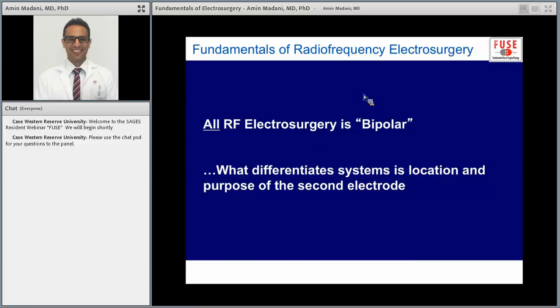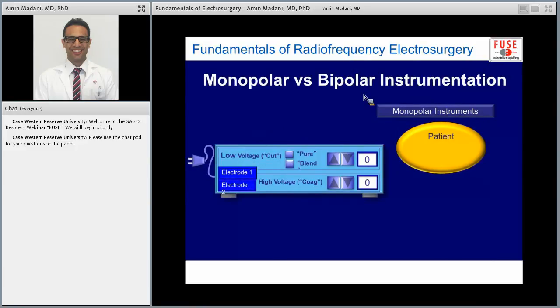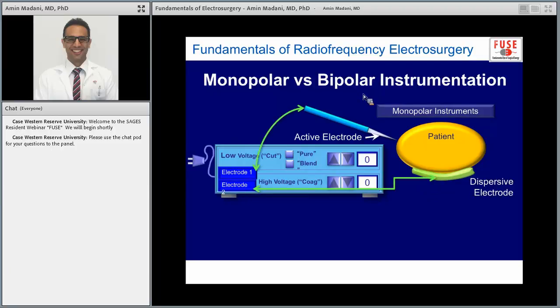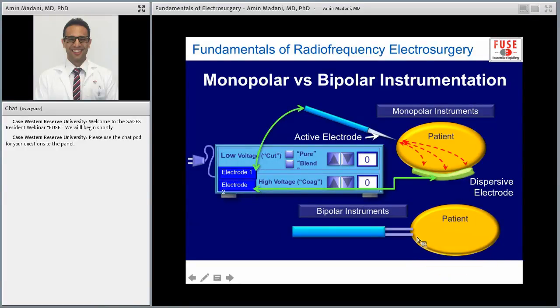I'm not going to talk about this too much because our next figure is going to talk about monopolar and bipolar energy devices, but essentially all radiofrequency electrosurgery is bipolar energy. It just depends on what you do with your different electrodes. You have your active electrode, which is your handheld tip, and then you have the pad that sticks on the patient, and then you have your circuit that goes round and round. Bipolar instruments are the same thing, but you have two active electrodes in the instrument. And so that's how you use radiofrequency electrosurgery.